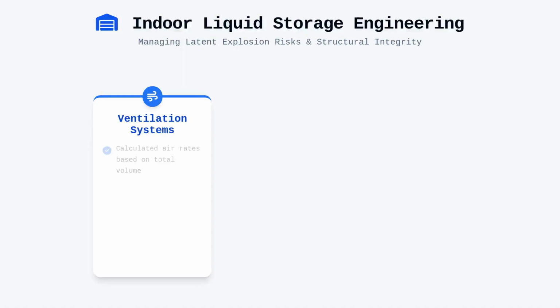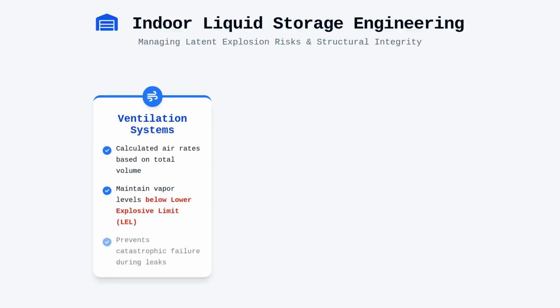When we construct indoor liquid storage areas or dedicated warehouses, we are essentially building a reinforced environment designed to manage a latent explosion risk. The codes specify rigid structural requirements to contain fires, but perhaps the most critical engineering feature is the ventilation system. We calculate these rates based on the volume of air required to maintain the liquid's vapor concentration well below the lower explosive limit, ensuring that a leak does not immediately result in a catastrophic failure.